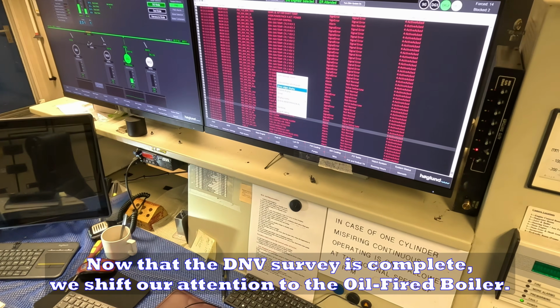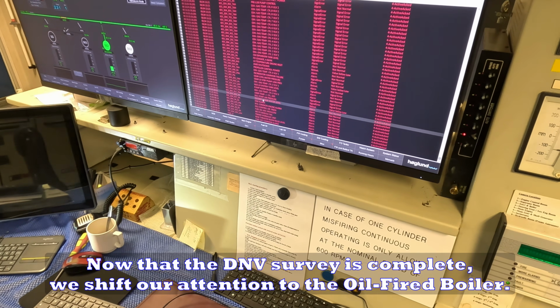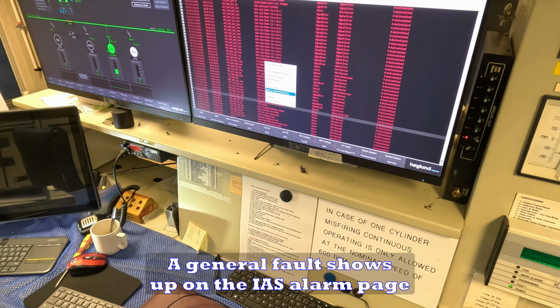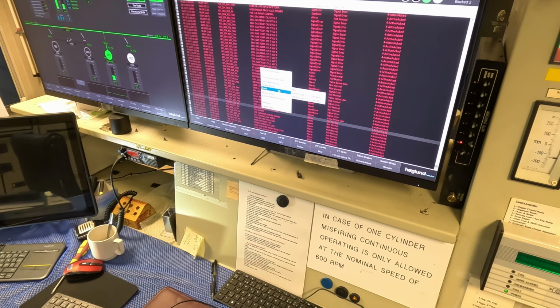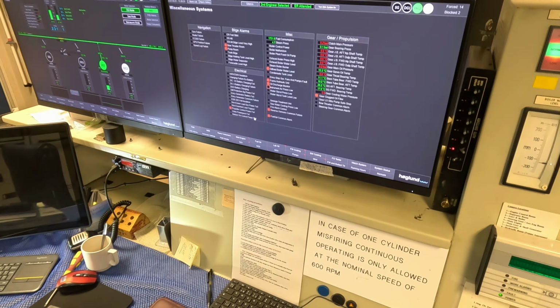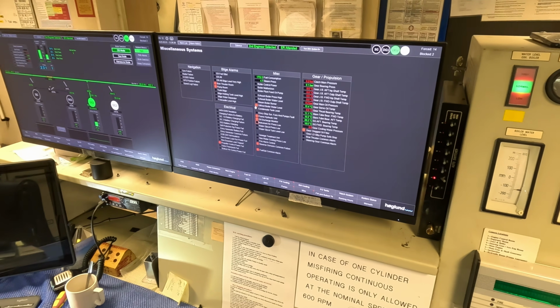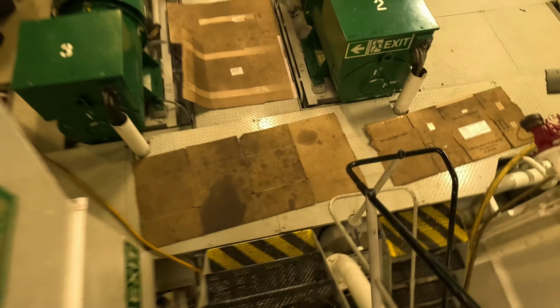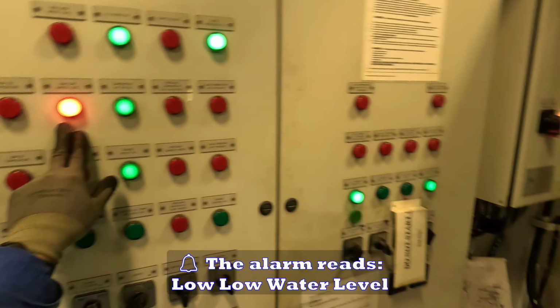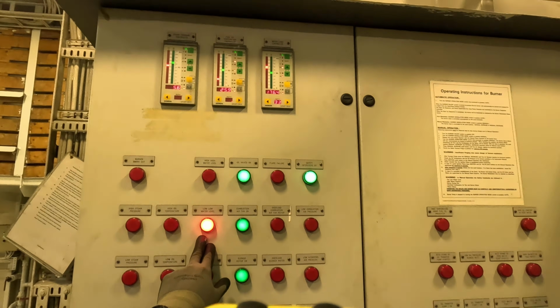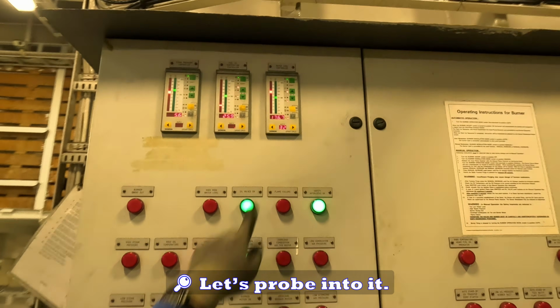Now that the DNV survey is complete, we shift our attention to the oil-fired boiler. A general fault shows up on the IAS alarm page. The details are at the boiler main control panel. The alarm reads, low low water level. Let's probe into it.